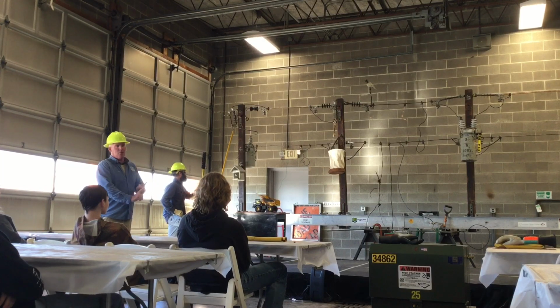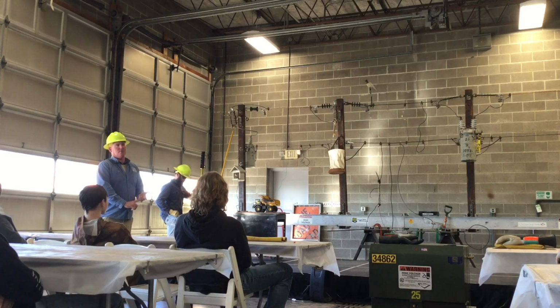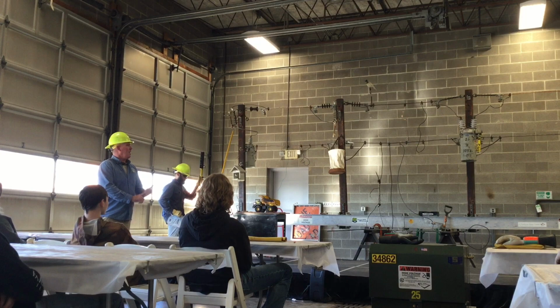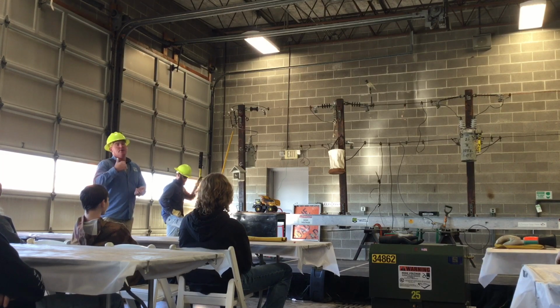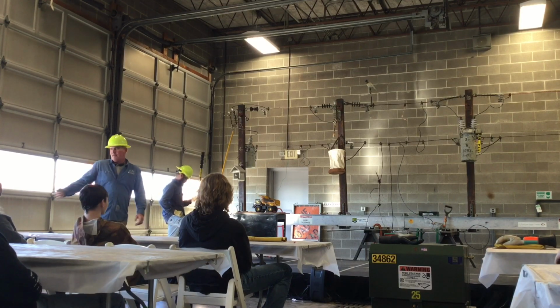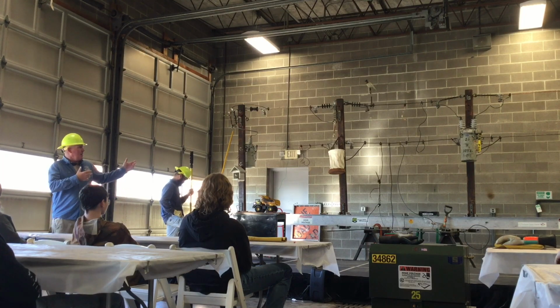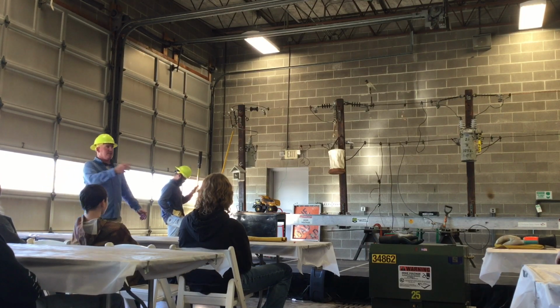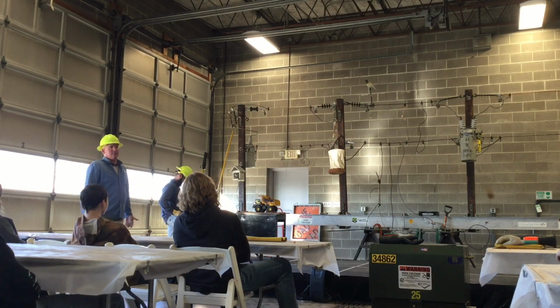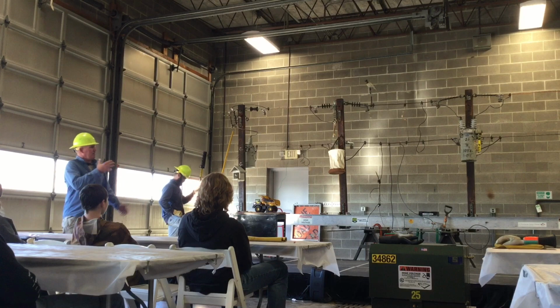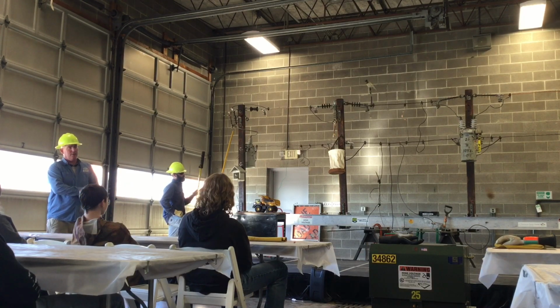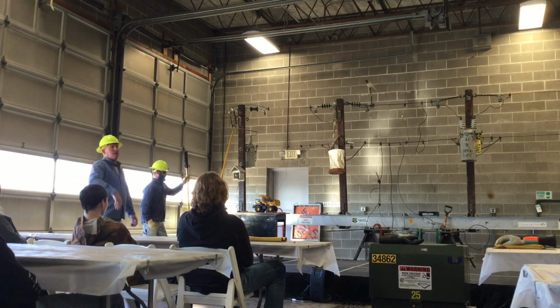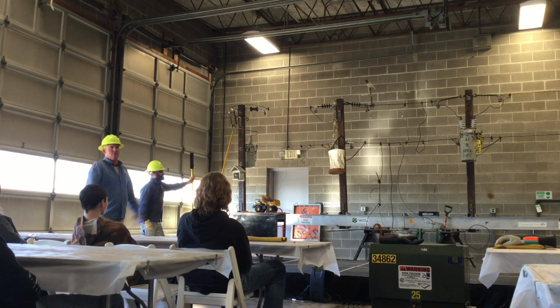So anytime a car hits a pole, I'm not gonna say anytime, it's designed to where if a car hits a pole, a limb falls in the line, a squirrel gets into a transformer, whatever, it's gonna open really fast. Boom. It's gonna open and then it's gonna try to reclose. And it'll do that 3 times. And the reason that we have these is if every time a squirrel got on a transformer and the power locked out, and let's say on a main 3-phase circuit we got 400 or 500 customers on it, there's gonna be a lot of people unhappy, right? So the breakers are designed for the fault to clear, hopefully, because a lot of faults will clear themselves. For the fault to clear, close back in, everything goes back to normal, nobody's day's messed up without power, right?